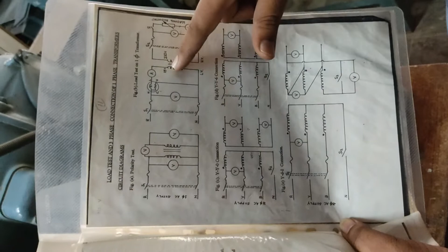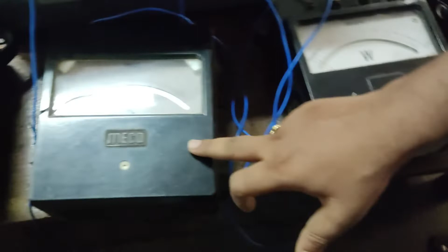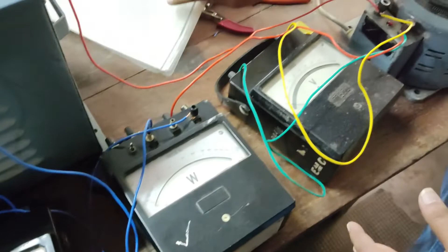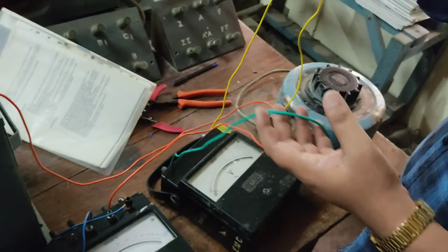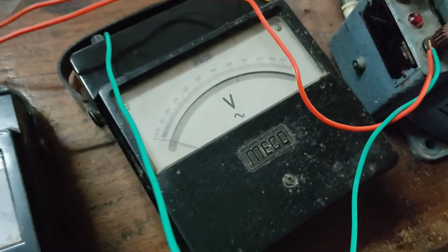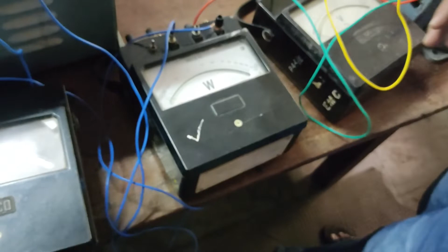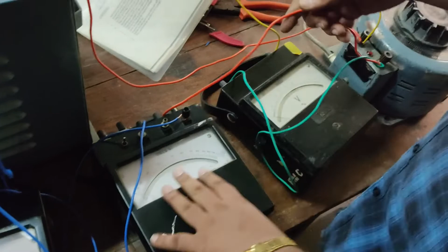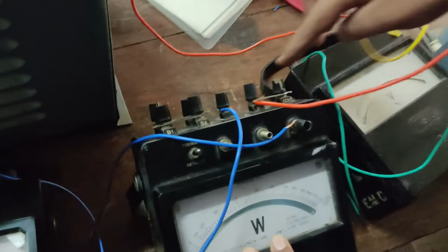Coming to the supply side, the variac is this one. This variac is directly connected to this transformer through the wattmeter and ammeter. So this is the input supply, and this is across the supply. The 0 to 300 voltmeter I have connected across the variac. And later we have to connect a wattmeter in phase with the supply. See this, the phase terminal is connected to the M of the wattmeter, and M and C are shorted.